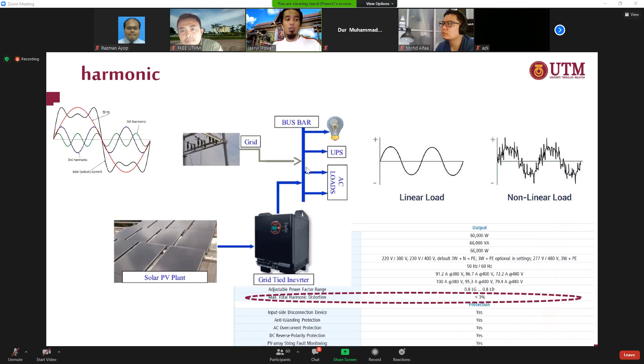Last but not least, the most critical one is in terms of power factor. In the real case study, the transformer load profile shows that the power factor drops significantly when we have PV, because the main task of PV is to generate real power. The reactive power is actually controlled by the inverter, not the PV. The PV itself only generates real power.